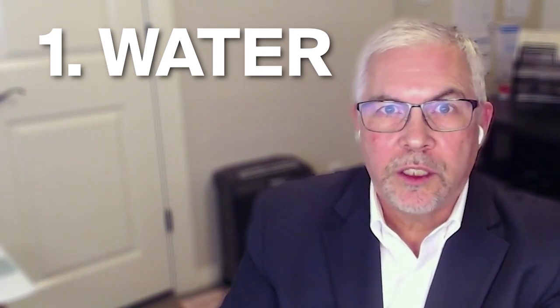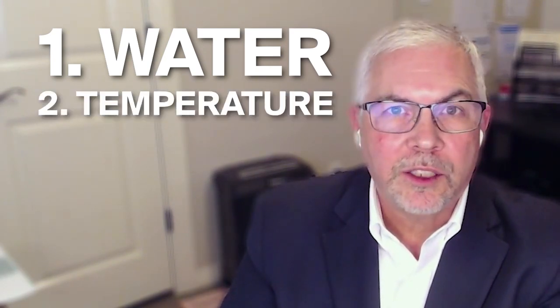They work together. It's generally accepted that the cellulose is the weakest part of that insulation system. When I say weak, I just mean it's going to age faster and reach what we'll call the end of life faster than the liquid will. Having said that, the electrical grade insulating papers that we use are very good electrically. But there are two main aging catalysts of cellulose, the paper. One is water. Water tends to cause the cellulose to break down. And second is temperature. If we increase the temperature, we increase the aging rate. If you increase either of them, the aging rate increases.